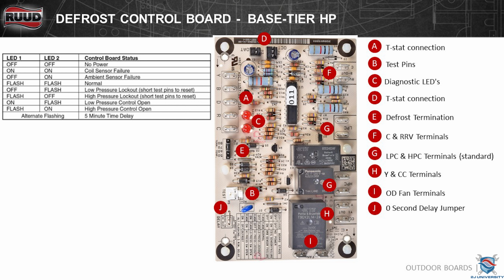This is that same board on your base tier system. Just kind of want to walk around this board a little bit. You got your Y1 out there. You have your high pressure control, low pressure control. You have your reversing valve here, your low voltage connections over here, your test pin, your defrost termination temperature. So pretty basic board, pretty simple.